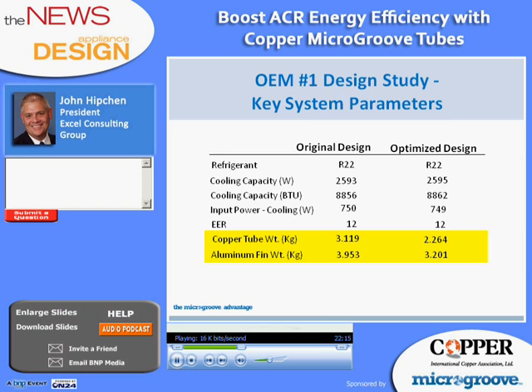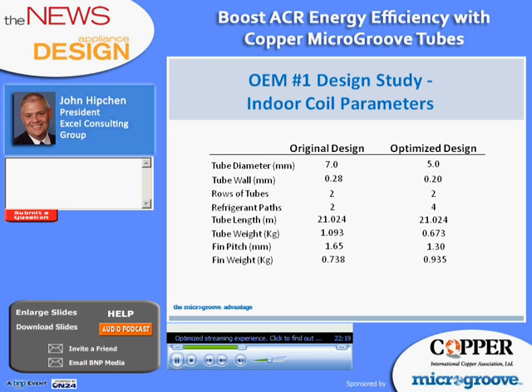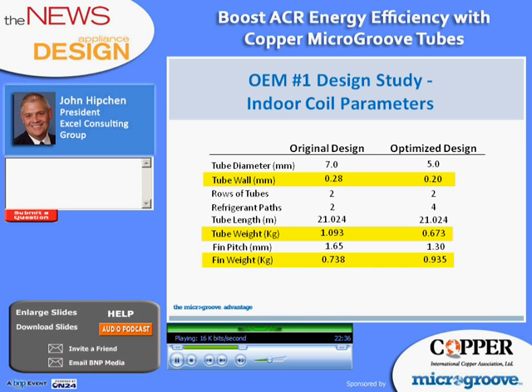So let's look closer now at each of the coils used in this system. In the cooling mode of operation, this is the indoor coil, and it's acting as the evaporator. Let's first compare the factors that we know translate most easily to material costs. And those factors are the weight of the tubes and fins. Looking at the total length of tubes in each design, we see that we have the exact same total tube length for the original design as we have for the optimized design. If we add up the lengths of each tube in the coil, that is the number we're talking about here when we refer to total tube length.